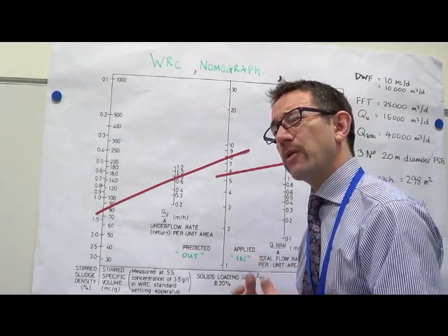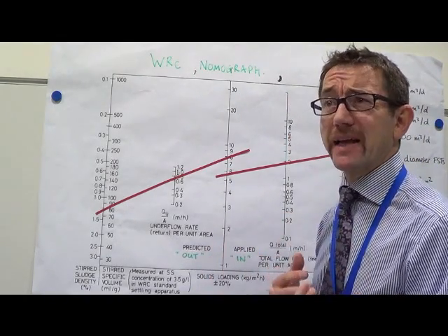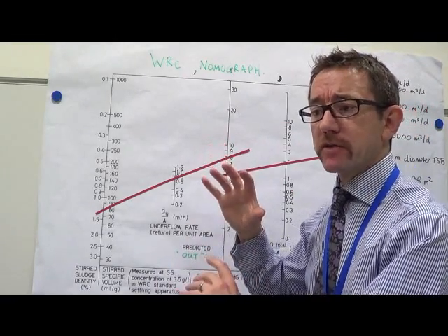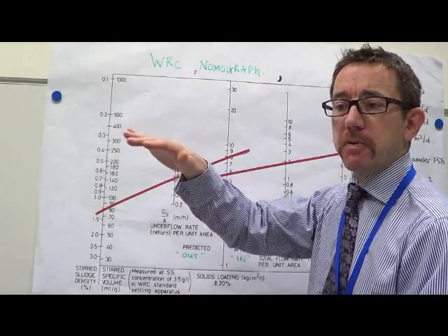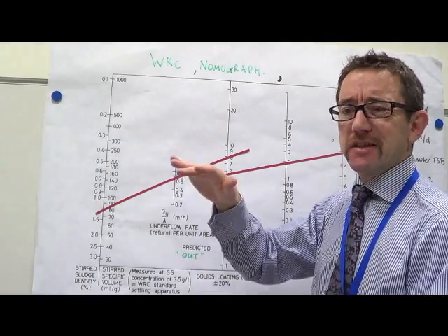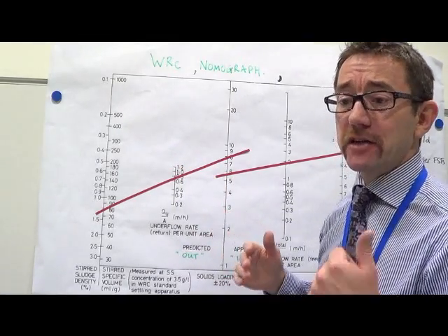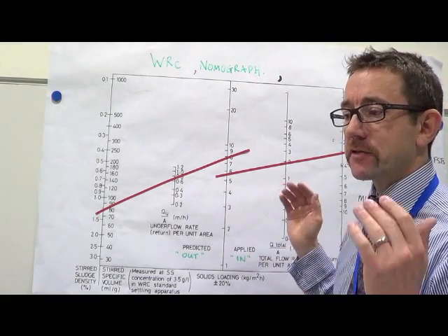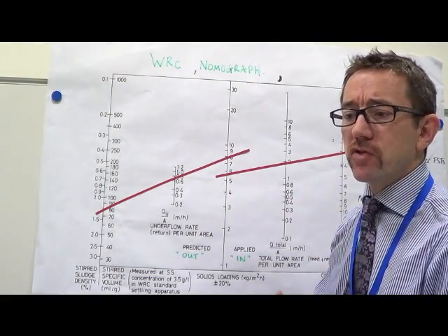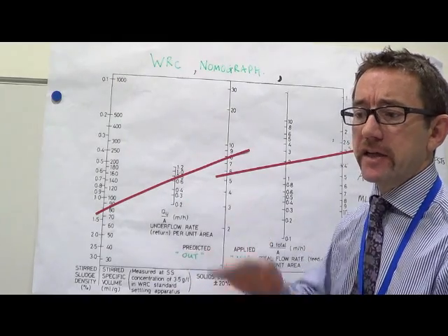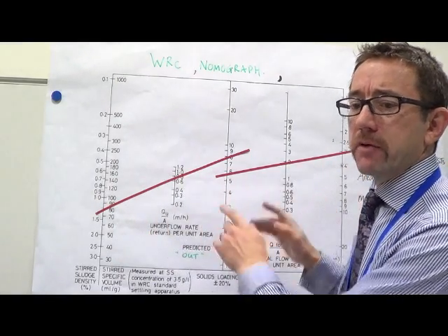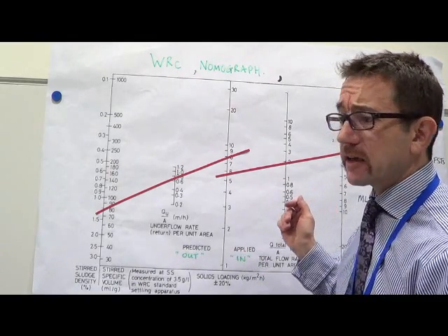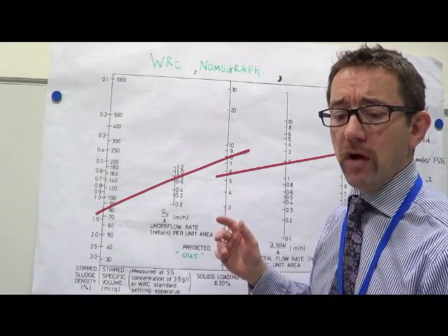Some people say things like, well, I like to run with a bit of a sludge blanket. If you remember back to our what goes in must come out situation, if you've got a deepish sludge blanket in your tank, there's something not quite right, unless it's under massive storm conditions and it is very stressed. If it's normal dry weather and you've got a sludge blanket in your tank, then something's wrong in your setup and you need to have a look at it.